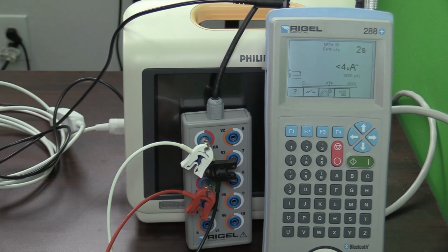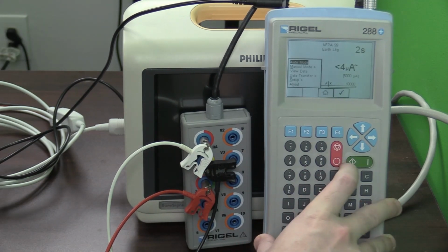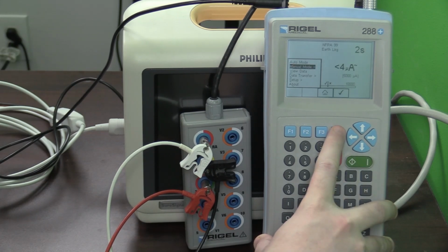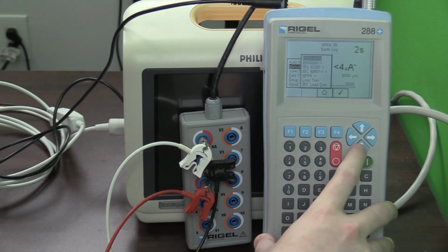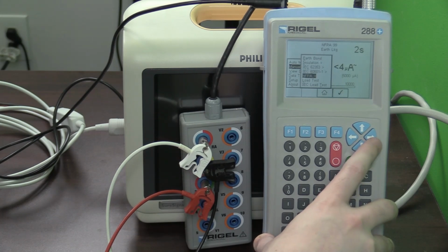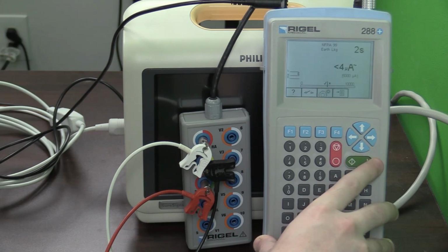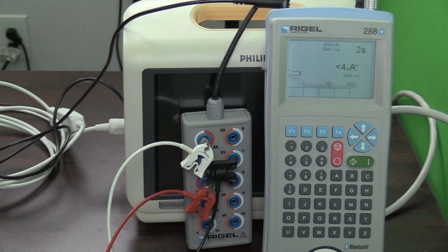So now that the device is powered on, you can select F4 to select your test mode. We're going to do manual. And today we're doing NFPA, so I'm going to scroll down to NFPA, open up that menu. And the first test we're going to run is earth leakage. Select F4 to select the test. Now that everything is hooked up, hit the green button to start the test. Now once the test is complete, you will need to note that the results are displayed as less than 4 microamps, and the check mark on the side is displayed, meaning it has passed the test.